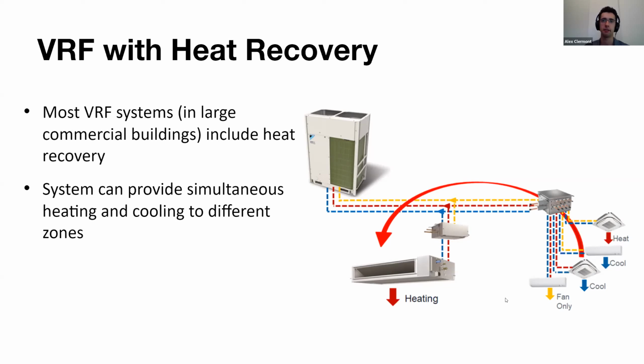Branch boxes come in very different shapes and sizes. And they're essentially the traffic cop for refrigerant. They'll let either liquid or gas through depending on what's required by the indoor unit. And again, this is the most common type in larger commercial buildings, but sometimes in smaller business applications as well, where the outdoor unit has three-phase power, they're also seen. VRF systems also allow a great deal of different kinds of indoor unit options, which Eric will go into in a little bit.